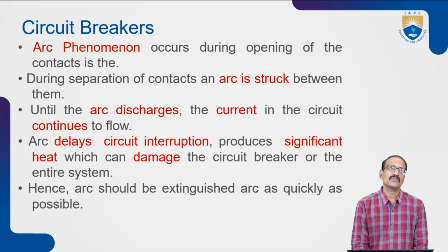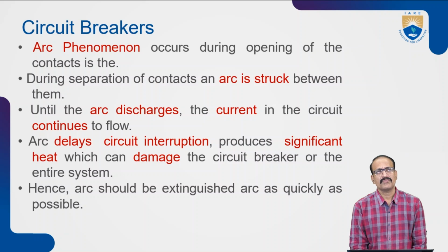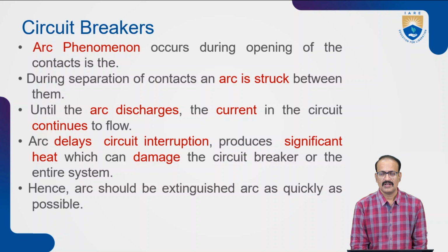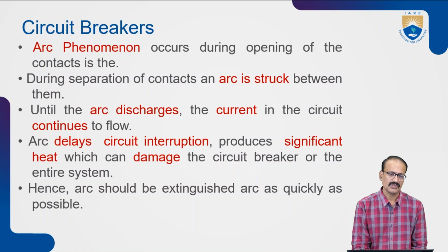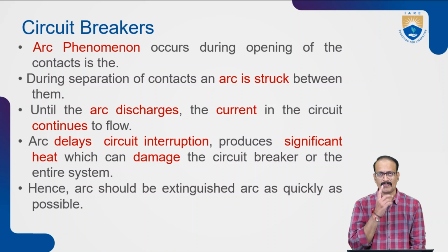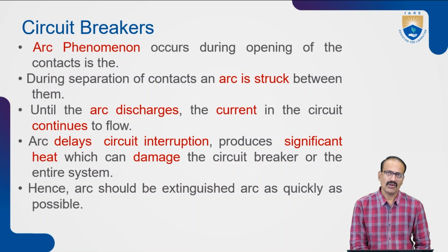During this arc, the disadvantage is not only the failure of the passage of electricity being stopped, but an enormous amount of heat is also produced. We are separating the contacts for the purpose of breaking the electrical supply or the circuit, and that purpose is not getting solved. This is a major challenge. Arc phenomena occur during opening of the contacts.